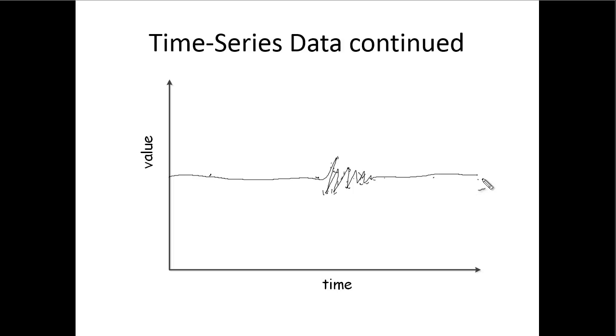Okay, and so it turns out that there's ways that I can do this. There's various methods that I can use that will not use a ton of space when I don't need to use a ton of space, and will use the space to capture dynamic stuff that I'm really interested in. Okay, and so one of those methods, there's a couple different things that I can do. And we've already talked about polling, right? So I'm polling my device. Let's say I poll my device every 250 milliseconds. So every 250 milliseconds I get a reading. Well, I don't want to store every one of those in the database, right? So one of the things I can do is I can do exception reporting.